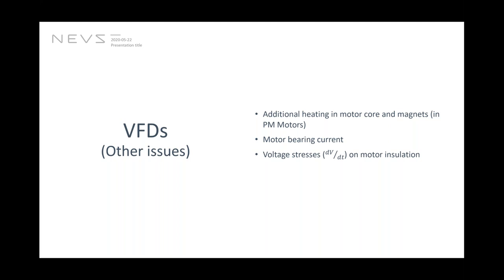So we have to be very careful that VFDs with pulse width modulation are switching the voltage waveform, or even the current waveform, especially voltage, quite fast, in the range of kilohertz. So that will impose slightly more copper losses as well as core losses, and it especially affects the magnet losses in a permanent magnet motor. So these additional losses need to be taken into account. What that means is that you probably need to oversize the motor for the application so that you don't heat it up so much, or you have to have a better way to cool it so that those losses are carried out of the motor.